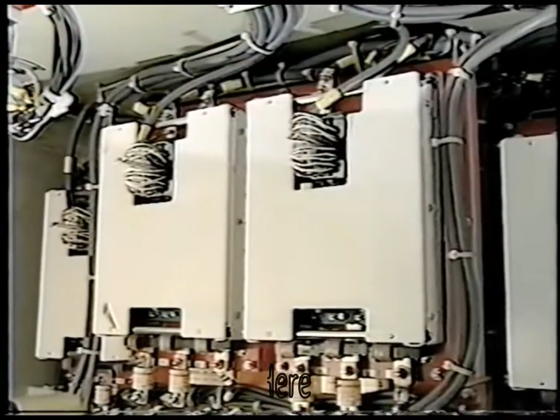The alternator blower thermal overload device, ABOL, monitors the blower current and opens the circuit in the event of an overcurrent condition. The ABOL is equipped with a reset. The equipment blower panel, EBP, and the radiator fan panel, RFP, send out altered 3-phase current to control motor speed. The 2 panels are interchangeable.